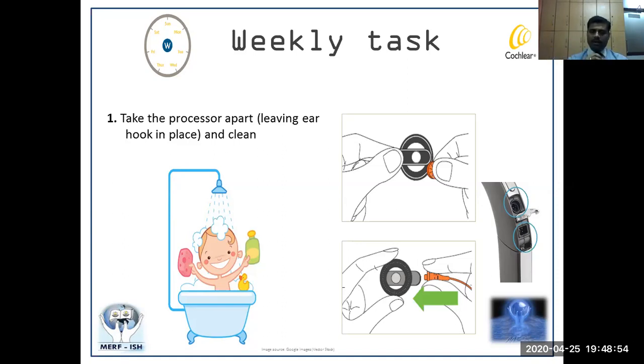The oil you apply also gets onto the transmitting coil, and when you put oil on it, it attracts a lot of dust. This dust settles between the screws of the magnet and the transmitting coil. If you don't clean it, at some point you may not be able to remove the magnet from the transmitting coil, and you may have to change the entire transmitting coil. Or if you put more pressure to remove the magnet, you ultimately damage the entire transmitting coil.